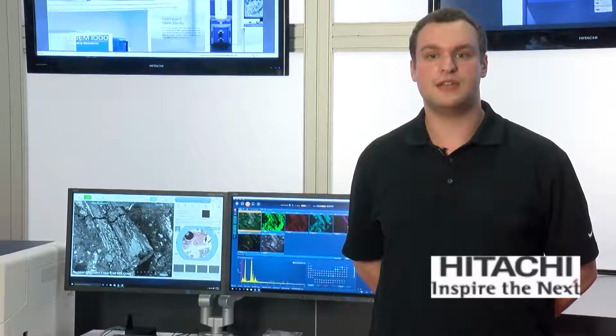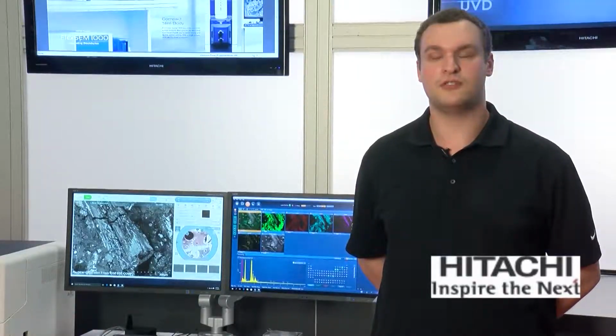So the entire optical system of this scanning electron microscope has been redesigned to produce higher emission currents which give us increased signals from our samples. Furthermore, the lens aberrations have been minimized such that a point resolution is 4 nanometers. Using these newly designed electron optics, auto functions have also been improved, such that auto brightness and contrast and autofocus together only take 5 seconds. Automatic filament saturation, aperture alignment, and stigma correction are also possible with this instrument. All of these functions come together to make operation easy and intuitive even for the novice user.